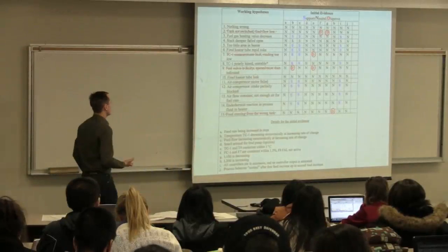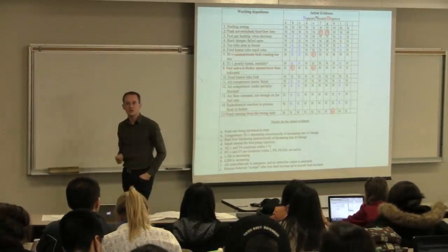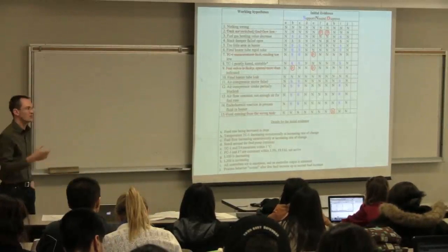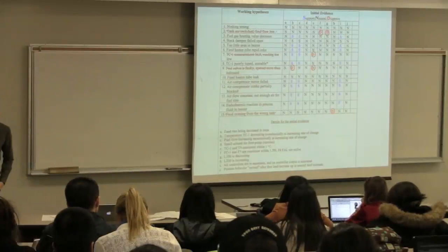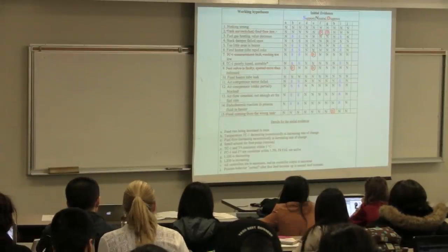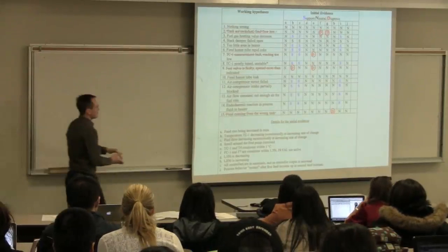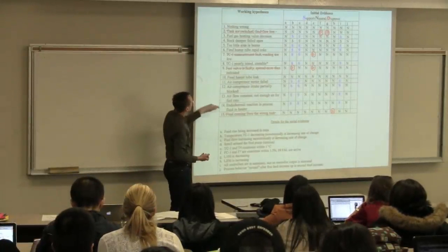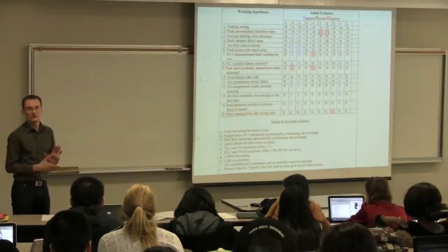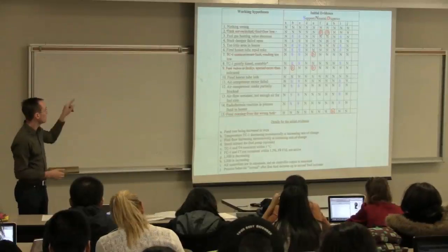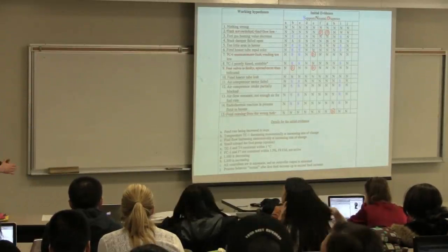And then a 14th one down here is we've got some impurity coming in our feed that's actually causing an endothermic reaction in that pipe in the fired heater. So while the material should be being heated, there's actually some side reaction taking place that's consuming the heat that we're adding. So that could be a valid reason. These are your hypotheses that you write down. And you could write down all of these without any information from the expert system. In the troubleshooting exercise, you could get through most of this table without any input from the actual client. These are just ideas that have come to your mind.